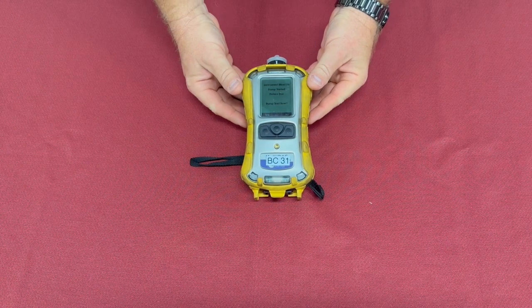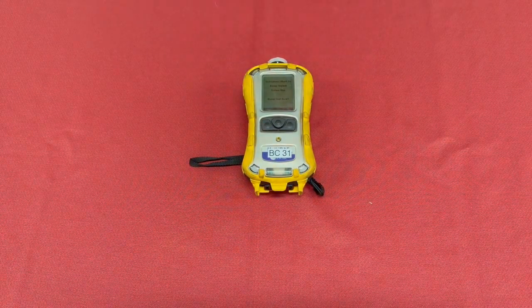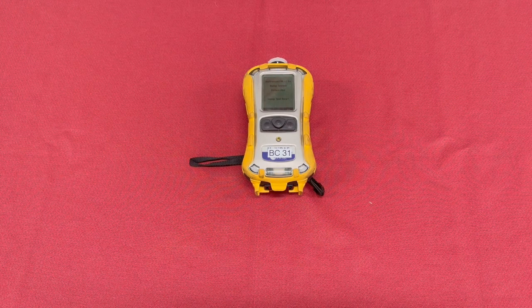All right, we've finished with that. It's done its fresh air setup and it's ready to go. What we've done with these meters is we've programmed them to require a bump test every 8 days and a calibration every 40 days. We generally would like to have all the meters checked every week. On the first weekly check of the month, we want to do a calibration. On all the rest of the weekly checks per month, we want to do a bump.